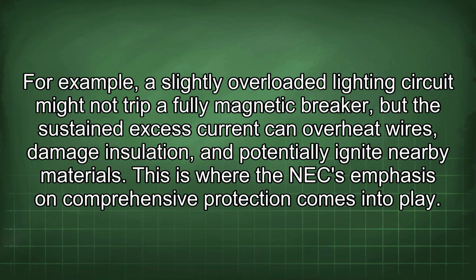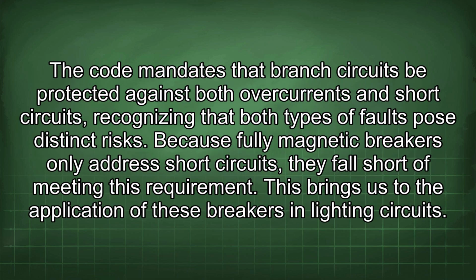For example, a slightly overloaded lighting circuit might not trip a fully magnetic breaker, but the sustained excess current can overheat wires, damage insulation, and potentially ignite nearby materials. This is where the NEC emphasis on comprehensive protection comes into play. The code mandates that branch circuits be protected against both overcurrents and short circuits, recognizing that both types of faults pose distinct risks. Because fully magnetic breakers only address short circuits, they fall short of meeting this requirement.